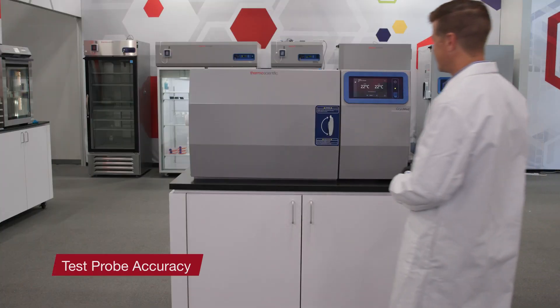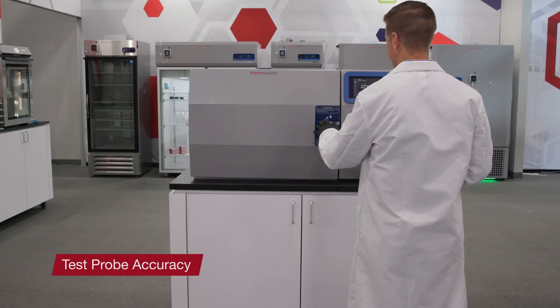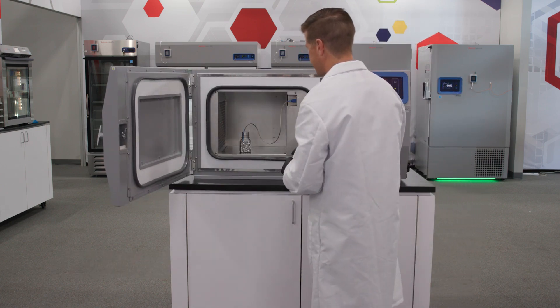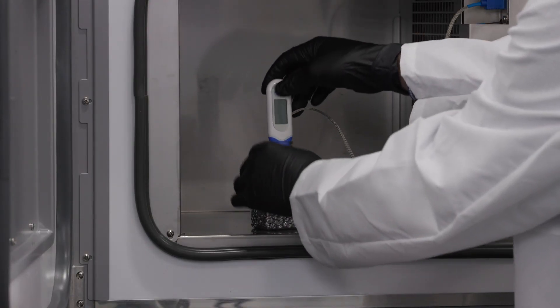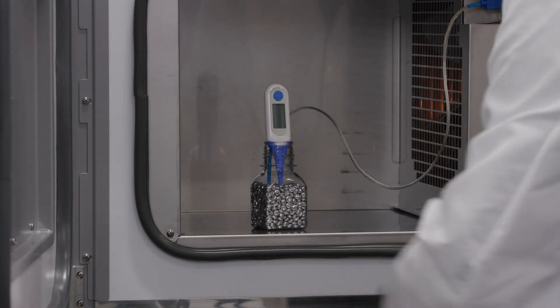It is recommended that you test the accuracy and calibration of your internal and sample probes by measuring the temperature in the chamber or sample by means of a secondary instrument.